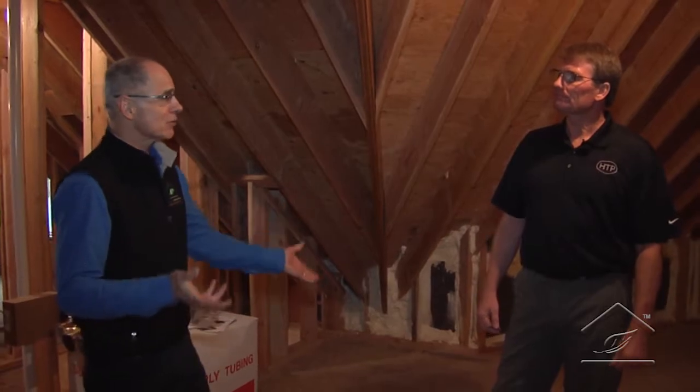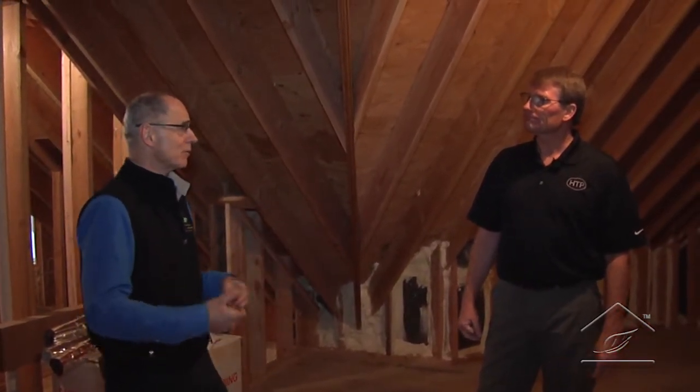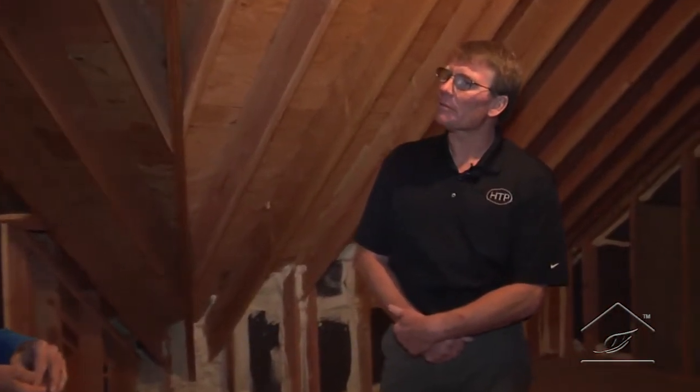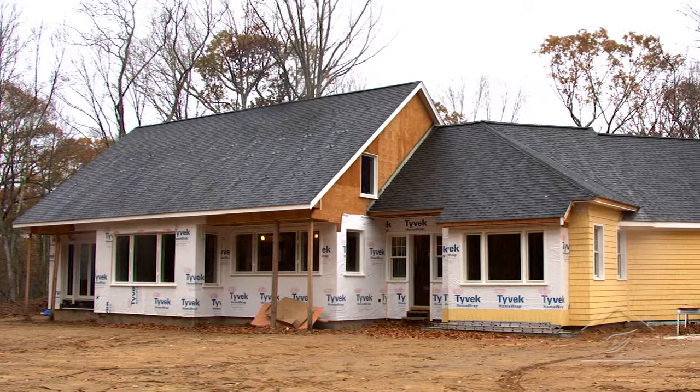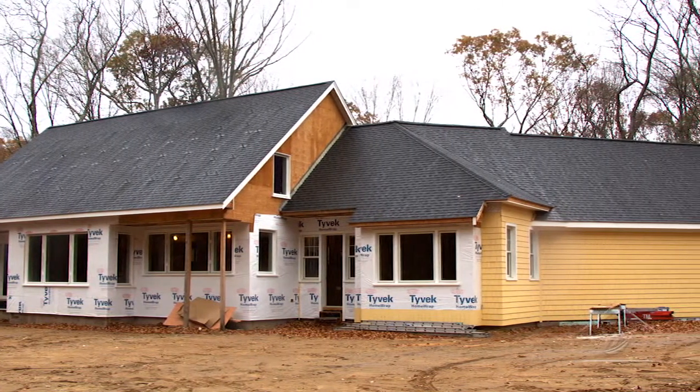Is there any weight constraints on that? Movable, manpower, doing an 8 footer over a 10 footer? Some contractors like to handle the 4x8s because it's common. It's like a sheet of plywood, and they're common to maneuver like that. And a 4x8 is under 150 pounds. You get to a 4x10, it's larger, it's heavier, it's above 150 pounds each. A little bit harder to handle, and you might need some extra people and some more equipment to do that. So that is a consideration that might be on a smaller contractor if he's going to install domestic hot water heating systems. Okay, well, that's good information.